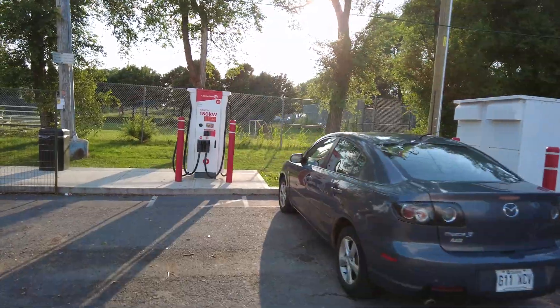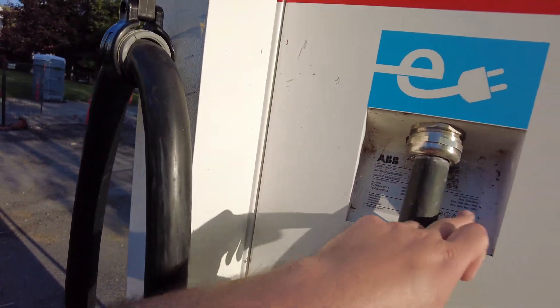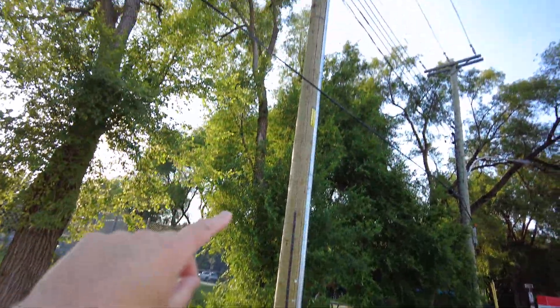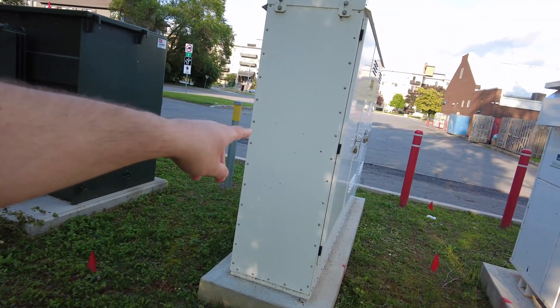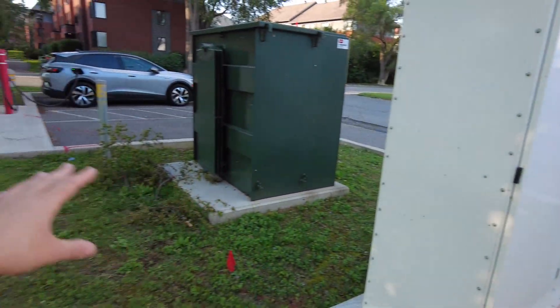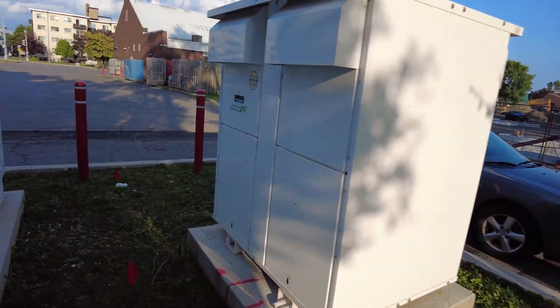We've arrived at the charging site by my house. Unfortunately there's a Mazda 3 blocking the site. So ABB Terra 184 — a lot of these were subsidized by the government. These are 300 amps, 480 volts, 400 amp nominal. Your grid connection is over here. Power comes down through here — there's your pole, your grid connection, your main transformer. There's an ID4 charging up there. You have your transformer here, your switchgear here, and more switchgear and equipment here. There is no diesel generator, there are no tanks. If you had a diesel generator here, there would be some sort of exhaust pipe and a diesel storage tank. But again, there's no diesel generator at this charging site.